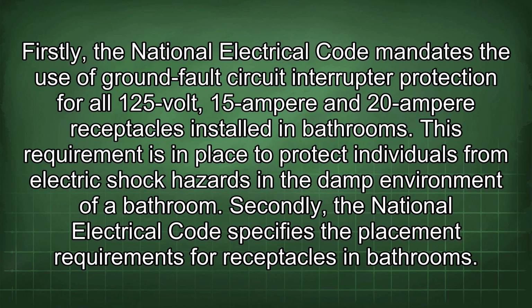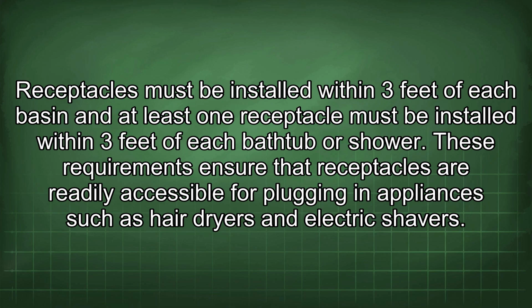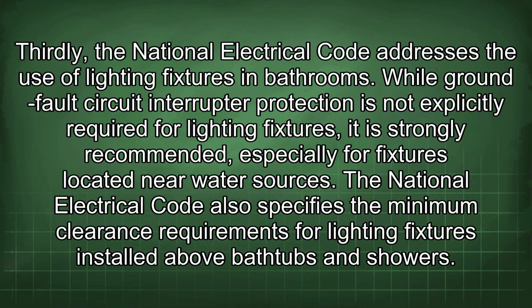Secondly, the National Electrical Code specifies the placement requirements for receptacles in bathrooms. Receptacles must be installed within 3 feet of each basin, and at least one receptacle must be installed within 3 feet of each bathtub or shower. These requirements ensure that receptacles are readily accessible for plugging in appliances such as hair dryers and electric shavers. Thirdly, the National Electrical Code addresses the use of lighting fixtures in bathrooms. While ground fault circuit interrupter protection is not explicitly required for lighting fixtures, it is strongly recommended, especially for fixtures located near water sources. The National Electrical Code also specifies the minimum clearance requirements for lighting fixtures installed above bathtubs and showers.